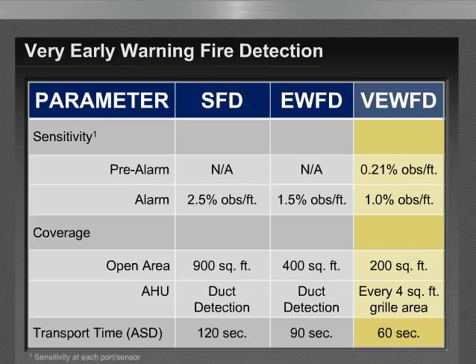But it may alternate as well. I mean, under certain configurations, we may see that the very early warning fire detection systems alternate between high and low drops every 400 square feet, but no less than 200 square foot between levels. And this is intended to address congested areas where obstructions might occur, and that the intent is then to provide sampling or detection above and below the obstruction. And in doing so, the spacing alternates every 200 square foot.